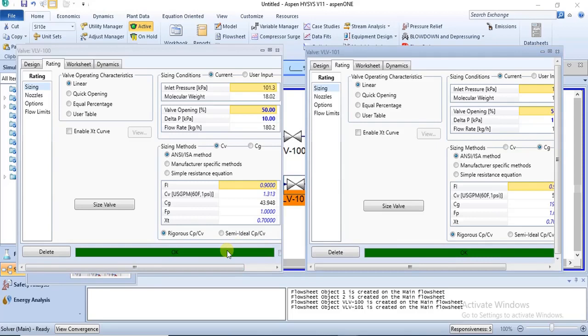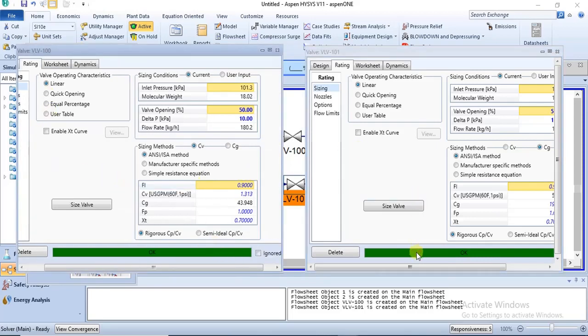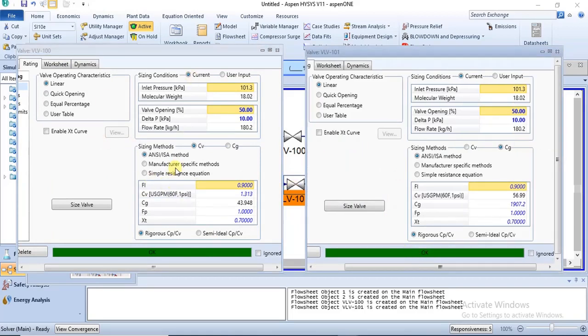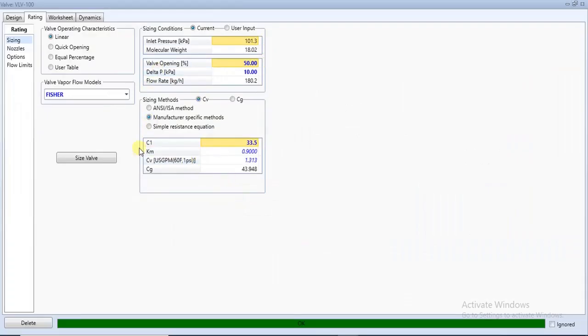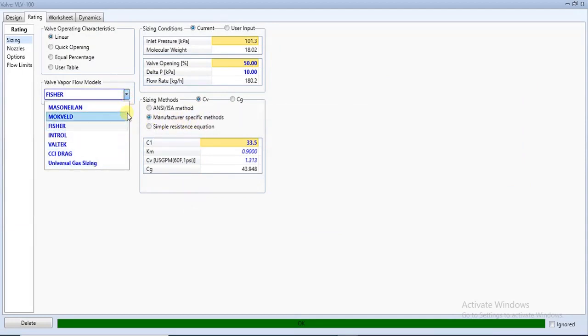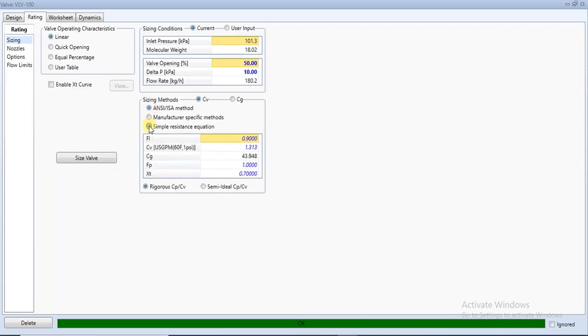In the valve sizing environment, you have several sizing methods available: the ANSI ISA method, manufacturer-specific methods, and the simple resistance equation. If you want to use a manufacturer method, click the radio button and scroll to choose the one you want. Most of the time, the ANSI ISA method is used for valve sizing, depending on your preference.